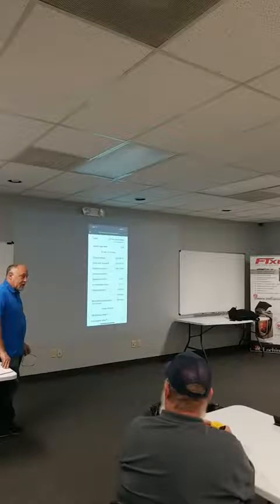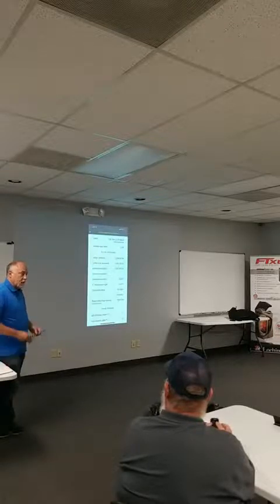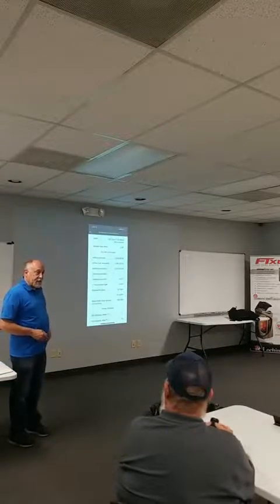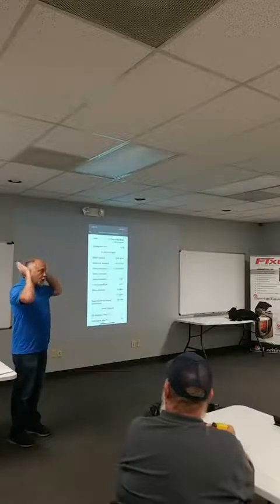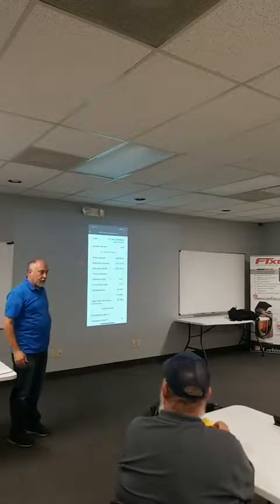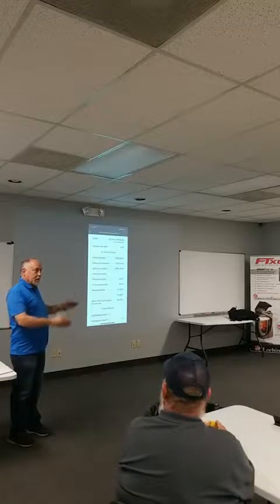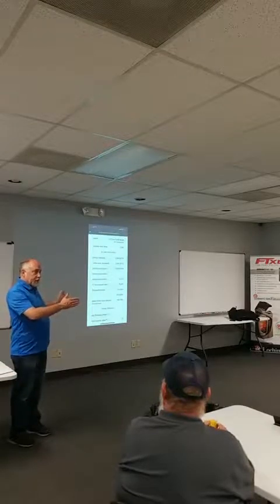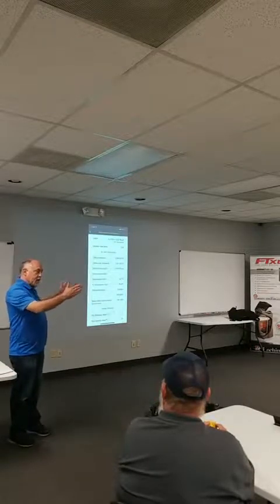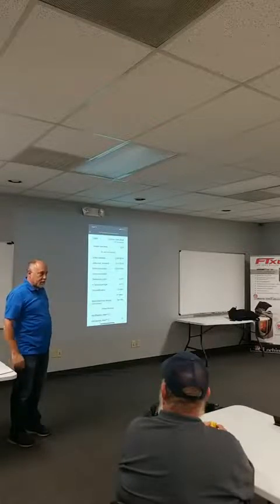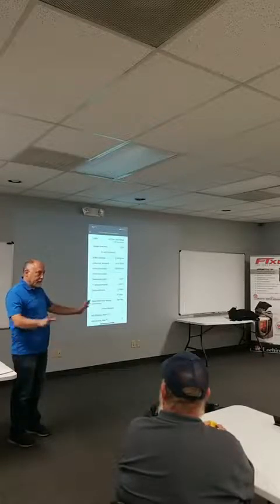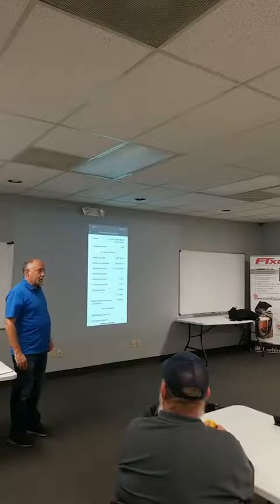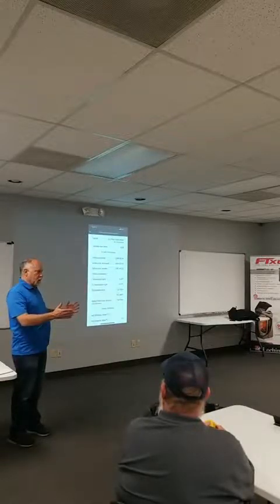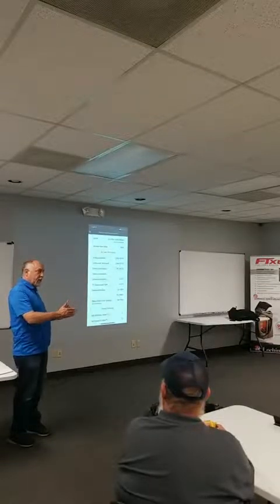An ECM fan is a constant volume machine with a variable mass flow. So in other words, if it's moving 2,000 CFM of air, it's got 2,000 boxes of air, it's just throwing one cubic foot box of air down the ductwork. It doesn't care what's in the box. If the box gets heavier, it's gonna move more mass. The lighter, it's gonna move less mass, but it's gonna move 2,000 boxes of air down the duct a minute. It doesn't care, right? ECM works off RPM and torque. ECM goes, ooh, these boxes are a little light. I'm gonna throw more of them.